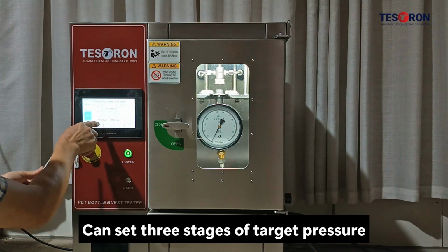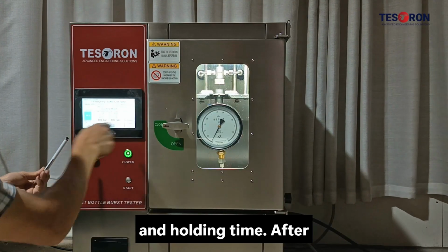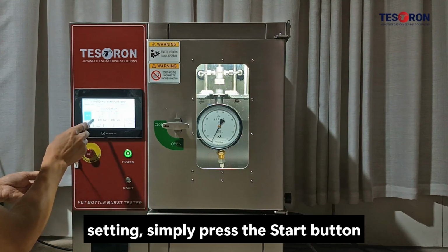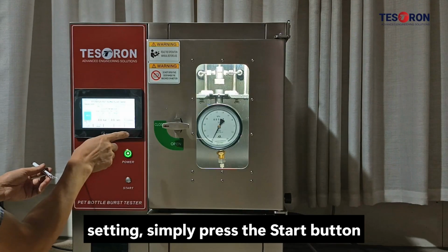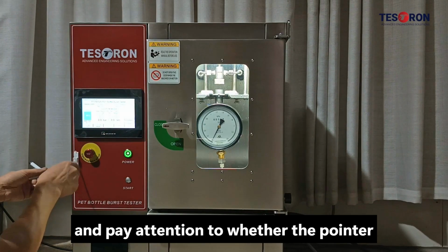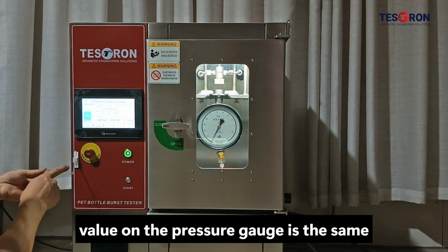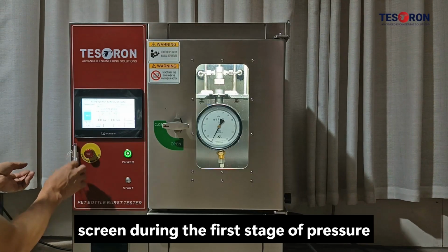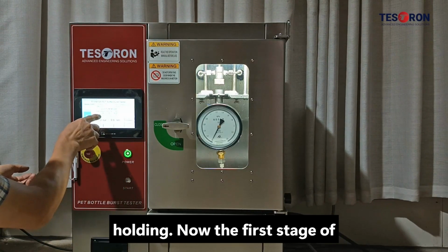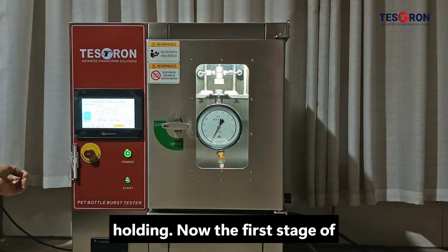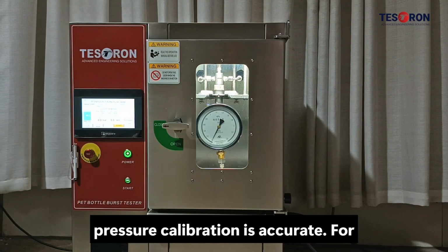Can set 3 stages of target pressure and holding time. After setting, simply press the Start button and pay attention to whether the pointer value on the pressure gauge is the same as the value displayed on the machine screen during the first stage of pressure holding. Now the first stage of pressure calibration is accurate.